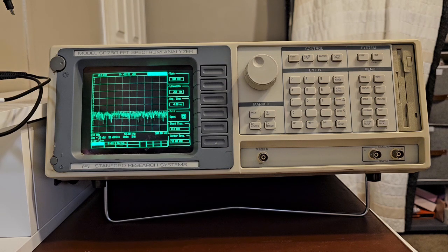It can measure any center frequency within the measurement range, subject to span and range limits. Its accuracy is 25 parts per million from 20 degrees Celsius to 40 degrees Celsius. Its resolution is span over 400.